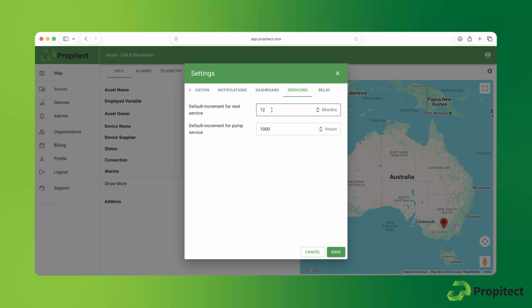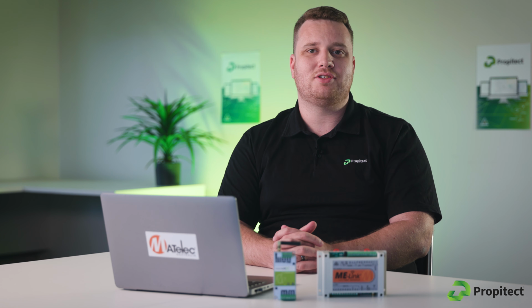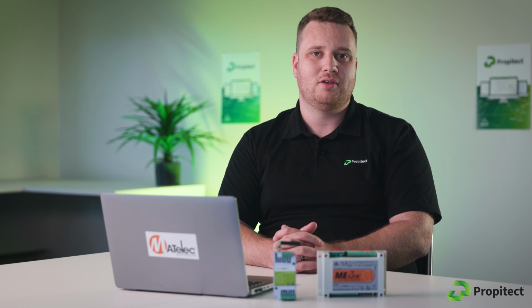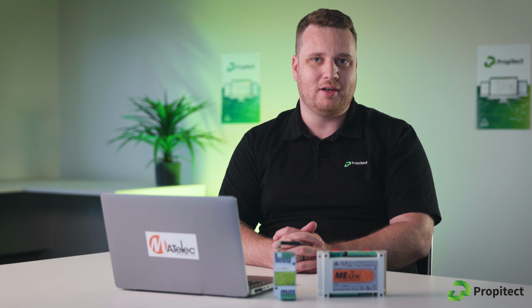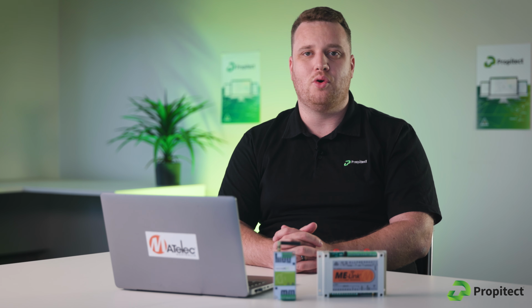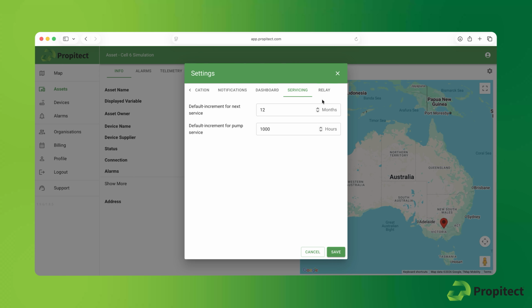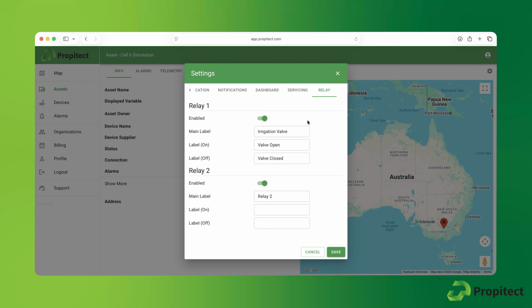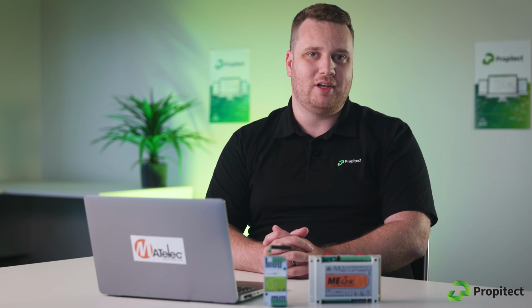Each Propitect asset can be configured for service scheduling based on either a set time interval or a pump run time. You can create standard service intervals here, so once a service is completed, the next due date will automatically populate. Depending on your device type, you may also have a Relay tab here. This allows you to configure relay output settings from the Control tab on the main asset screen. We'll explore that in another video.